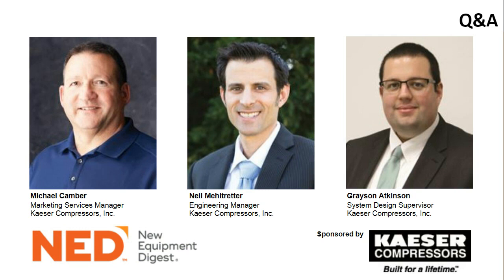Now, the question then would be, well, what if I had one dryer fail? Now I've got air going past one dryer that's not treated. Grayson mentioned an air main charging valve. If the air main charging valve was tied into a dryer failure alarm or a moisture content alarm, let's say, from a drain, you could shut that valve completely off in that line, and all the air would go into that second dryer, which would be sized for 100% duty cycle. So for many of our customers, that's how we're sizing things.